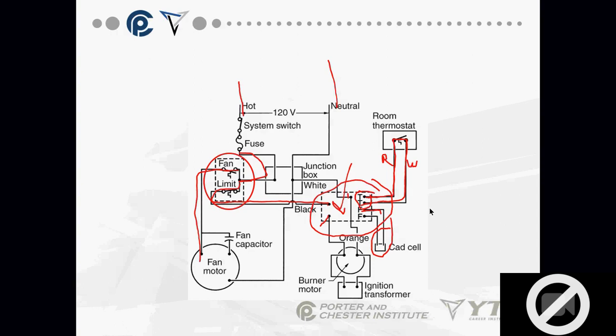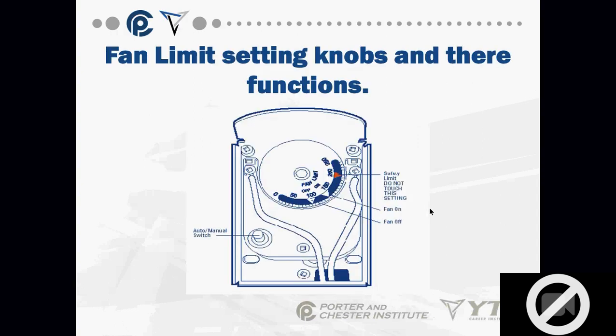Okay? So we're going to talk about more of the wiring on this. But any questions when you're looking at this? No, sir. Okay. There are several settings on the fan limit control. Okay, again, this one is set up, fan on. My furnace starts heating up. The first setting that it's going to go to is my fan on. Don't get confused and think about what my fan off is. My first setting that this is going to actually do anything with is fan on. This one, fan on, is set for 150.